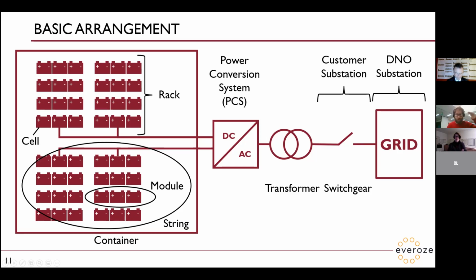In the UK we've got two levels of electrical infrastructure. National Grid, you'll have heard of - they're called the transmission network operator or transmission system operator, TSO, and they operate the really high voltage stuff, the massive overhead pylons, usually 132 kV and above. We also have distribution network operators, the DNOs - the Western Power Distributions, UK Power Networks, or others. There's about 5 or 6 of them across the UK, at a lower voltage, 33 kV and below, and they distribute at that lower voltage.